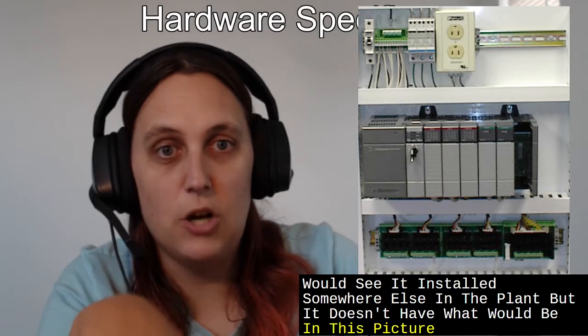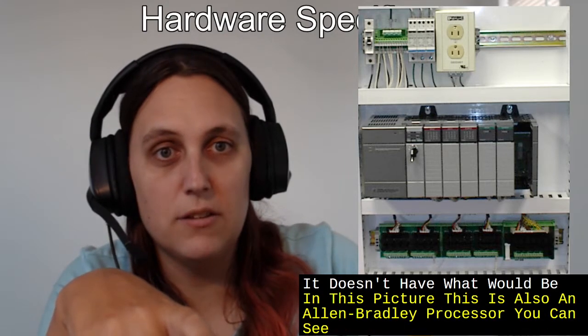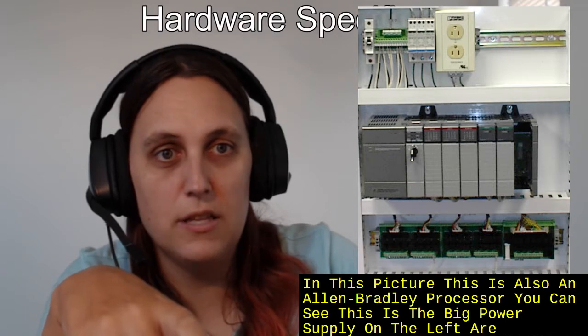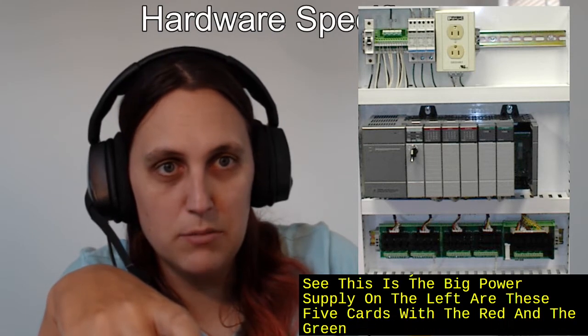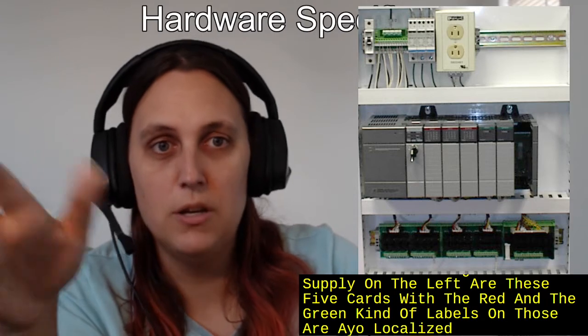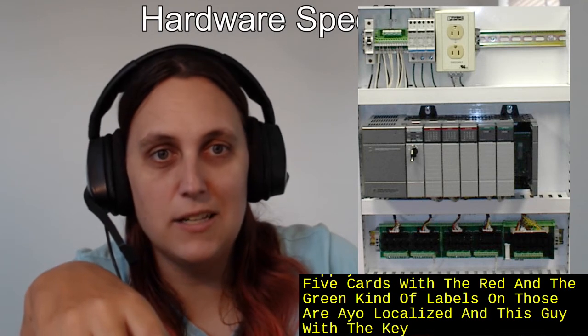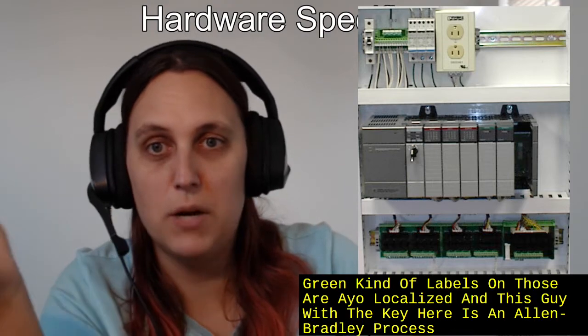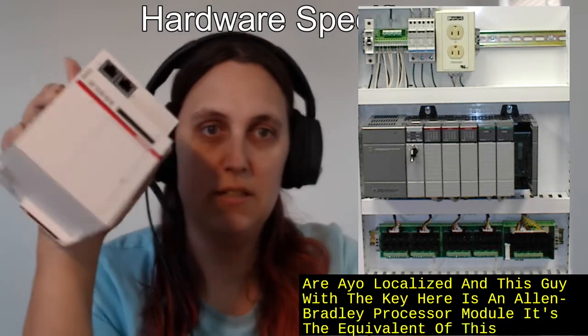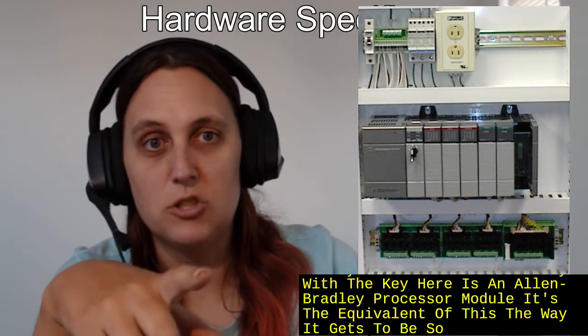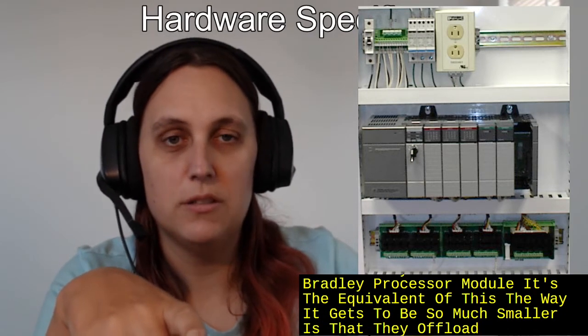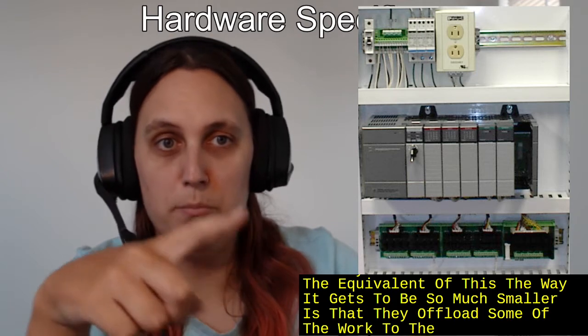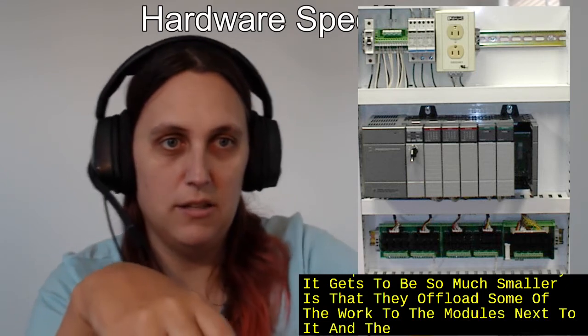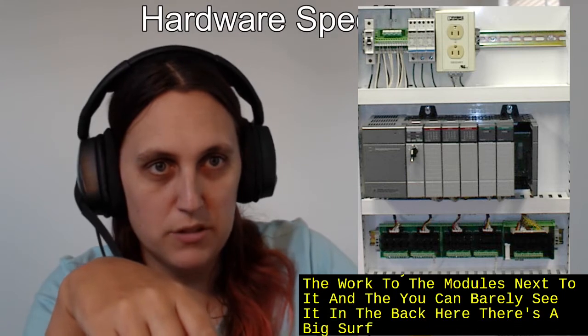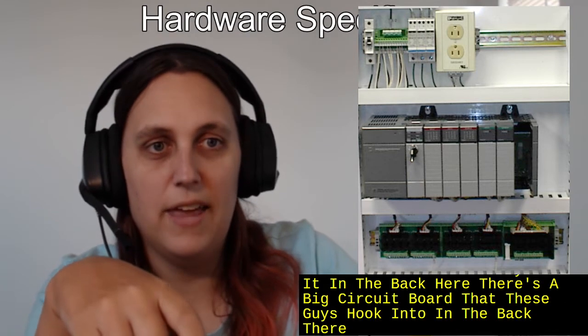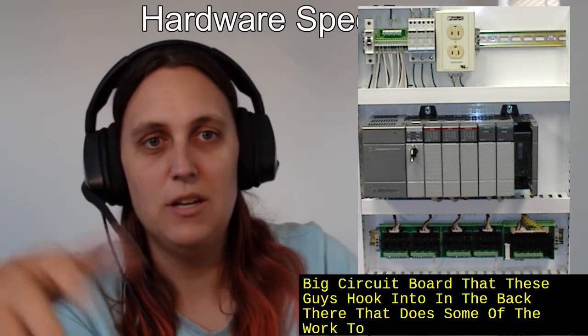In this picture, this is also an Allen Bradley processor. You can see this is the big power supply on the left there. These five cards with the red and the green labels on them, those are local I/O. And this guy with the key here is an Allen Bradley processor module. It's the equivalent of this. The way it gets to be so much smaller is that they offload some of the work to the modules next to it, and you can barely see it in the back here. There's a big circuit board that these guys hook into in the back there that does some of the work too. So that's how they get away with it.